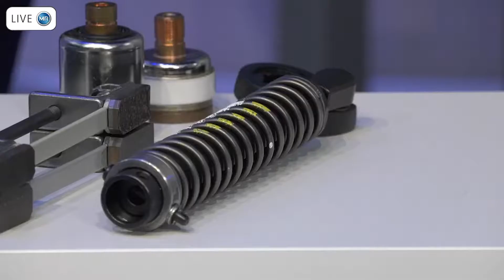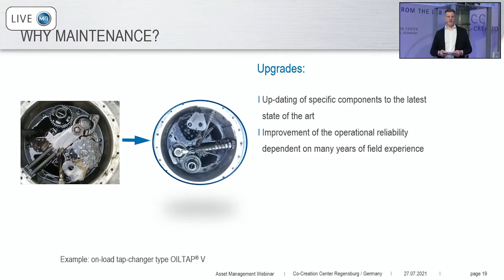However, the complete gear is completely newly designed. And the benefit is that this gear is completely maintenance free. Once it is installed, it must be replaced at 800,000 switching operations, which is the same interval as for the selector switch insert of the OILTAP V. These are just two examples, one from the OILTAP M and one from the OILTAP V. Of course, there are some more upgrades, but it is important to mention that we are not just pulling out the diverter switch insert, cleaning it, and putting it back. We carefully measure everything, check, and also upgrade these components for you.